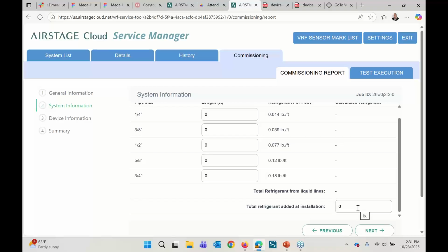Not only will it tell you, it will also store that information. We all know that if you're troubleshooting a leakage problem with VRF, knowing what your refrigerant charge should be is the most important number you need. In the past, you had to rely on someone writing it on the outdoor unit with a Sharpie marker or putting it in a design sim file you'd have to go find. With AIRSTAGE Cloud, it's now accessible—you know exactly where it is, available 24/7 anywhere on the planet.